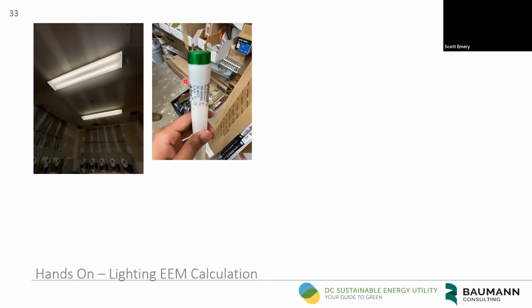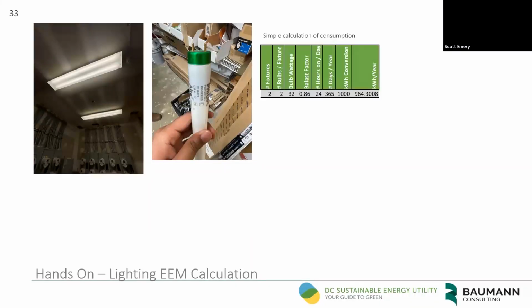So the very first thing you have to do in measuring the system, you've got to know what your initial case existing consumption is. So in here, we're showing that there's 2 fixtures, 2 bulbs, 32 watts per bulb. And then you have a ballast factor of 0.86. We're going to assume that it's running 24 hours a day, 365 days a year. Then we're going to convert it from watts to kilowatt hours. And then you have your total kilowatt hour per year consumption of 964.